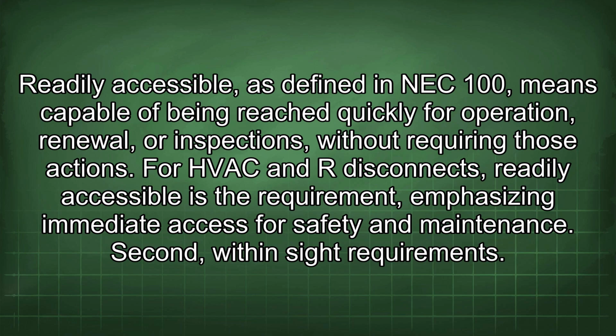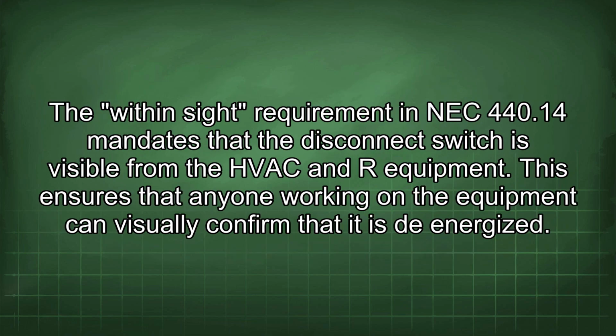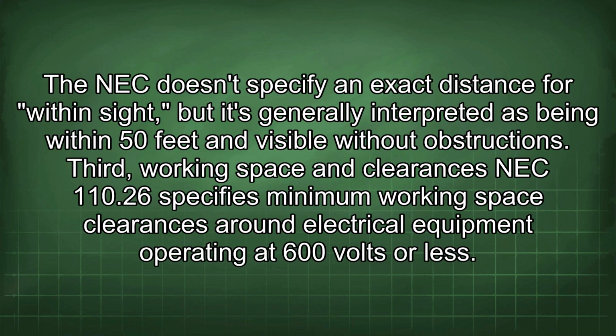Second, within-sight requirements. The within-sight requirement in NEC 440.14 mandates that the disconnect switch is visible from the HVAC and R equipment. This ensures that anyone working on the equipment can visually confirm that it is de-energized. The NEC doesn't specify an exact distance for within sight, but it's generally interpreted as being within 50 feet and visible without obstructions.